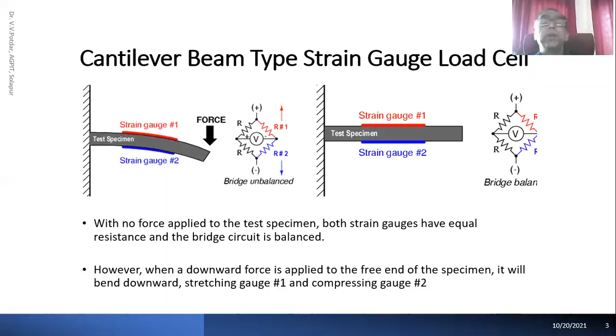So the same thing in statements: with no force applied to the test specimen, both strain gauges have equal resistance and the bridge circuit is balanced. However, when a downward force is applied to the free end of the specimen, it will bend downwards, stretching gauge 1 and compressing gauge 2, giving some output voltage. So this is the cantilever beam type strain gauge load cell.